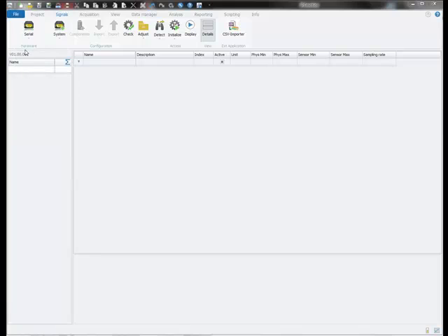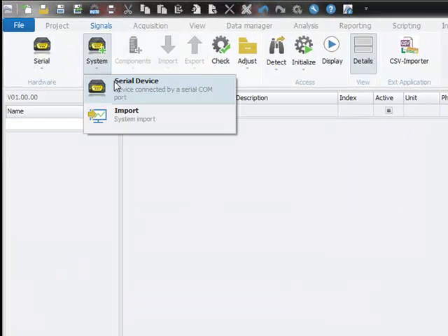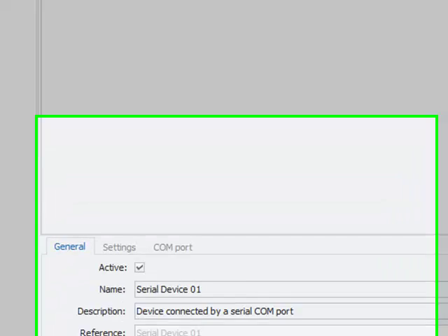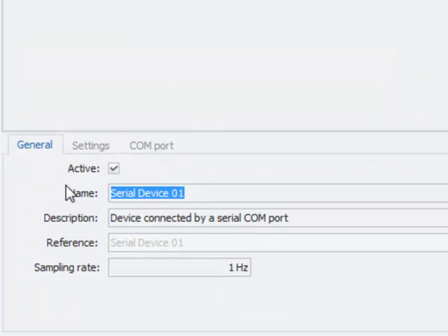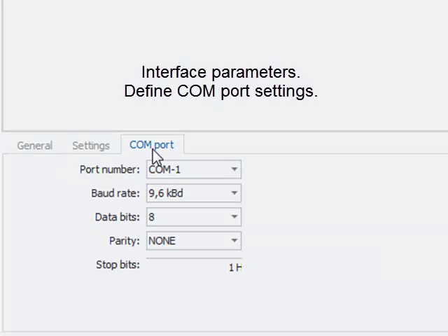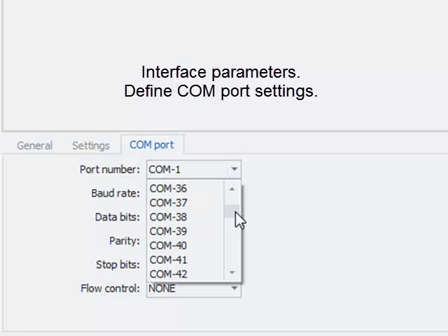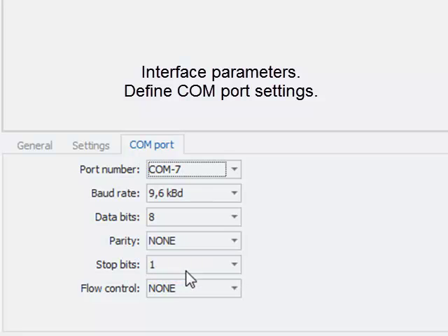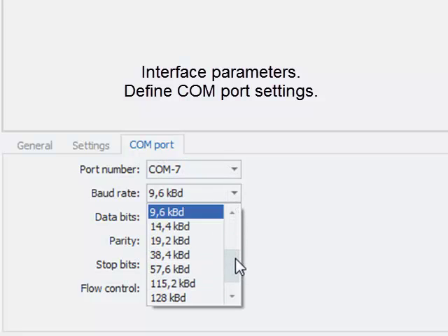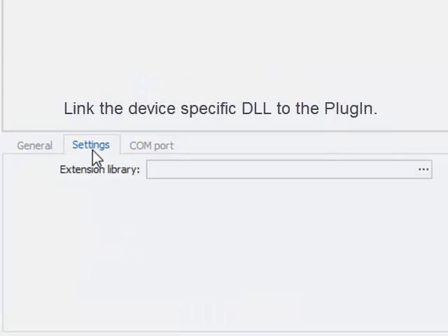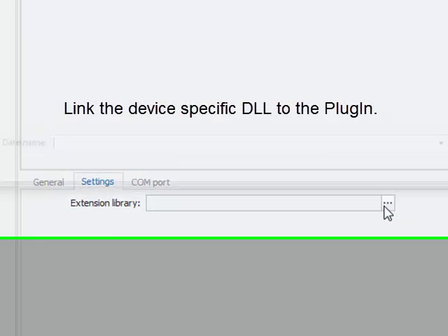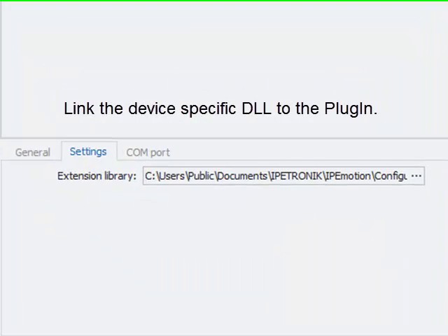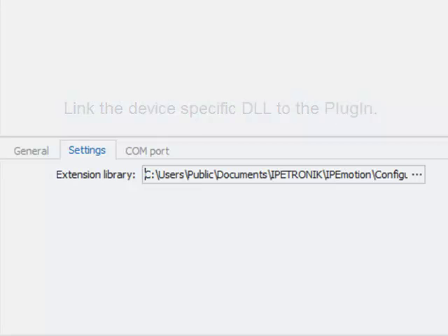Then I switch to the serial plugin and add a new serial device. I call this device NORMA 3000. In the COM port tab sheet, I configure the serial interface parameters which I take from the hardware manual of this device. In the settings tab sheet, I will link the NORMA power analyzer extension acquisition DLL to my plugin to enable the data communication.